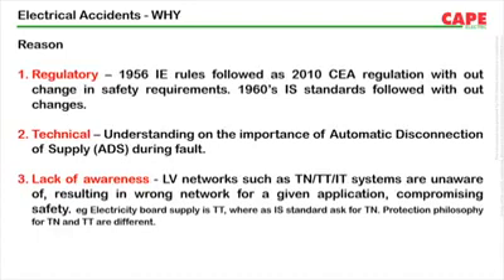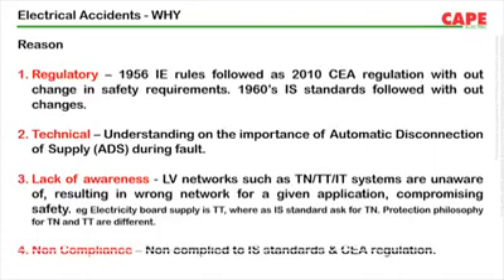This network called TT came into existence in the late 1960s. The problem is that the protection philosophy of TN and TT are different. So the utility has to be very careful in selecting a proper network for public electricity distribution. The fourth reason is non-compliance. We use low quality products due to less price and bypass the protective device due to nuisance tripping. I will explain these four points with examples.